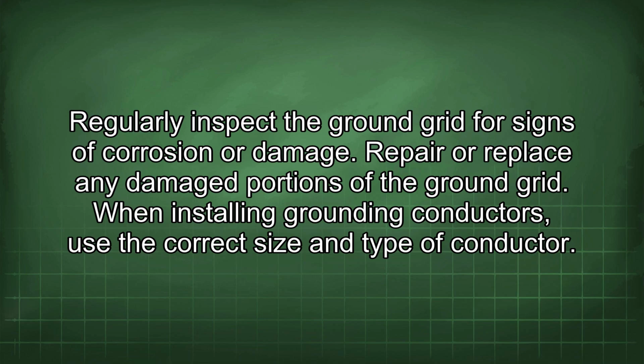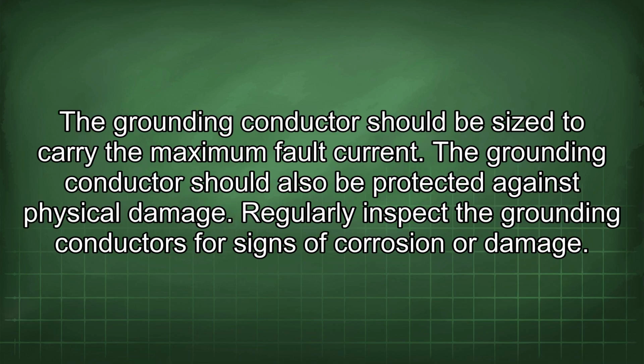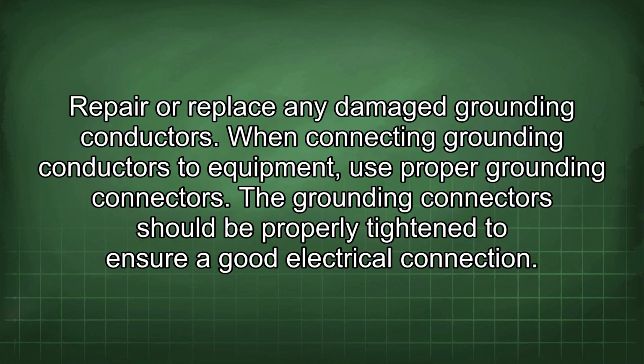When installing grounding conductors, use the correct size and type of conductor. The grounding conductor should be sized to carry the maximum fault current. The grounding conductor should also be protected against physical damage. Regularly inspect the grounding conductors for signs of corrosion or damage. Repair or replace any damaged grounding conductors.